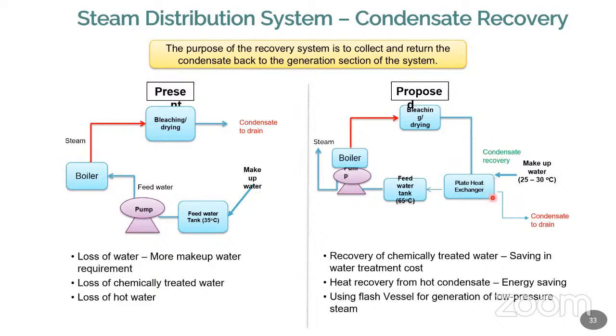I can take the heat and use it for my feed water tank. 35 degrees will increase to 65 degrees, so automatically a 30 degree increase in temperature. So how much fuel can you save? Again, it's going to be very simple: mass into Cp into delta T.